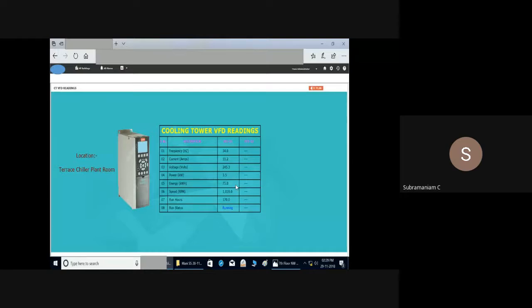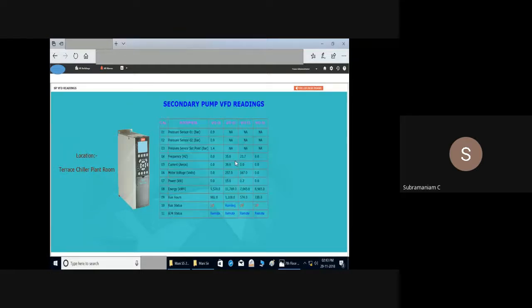Through Modbus, we get all this data. What is my frequency? It is running at 34 Hertz. My voltage is this, power is this, energy is this, speed is this, run hours is this. So by integration, we get all this value. For the secondary pump, my pressure set point is 1.4 bar and the actual value is 0.9, which means it will reduce it. My valves are closed, which means less chilled water flow is required.